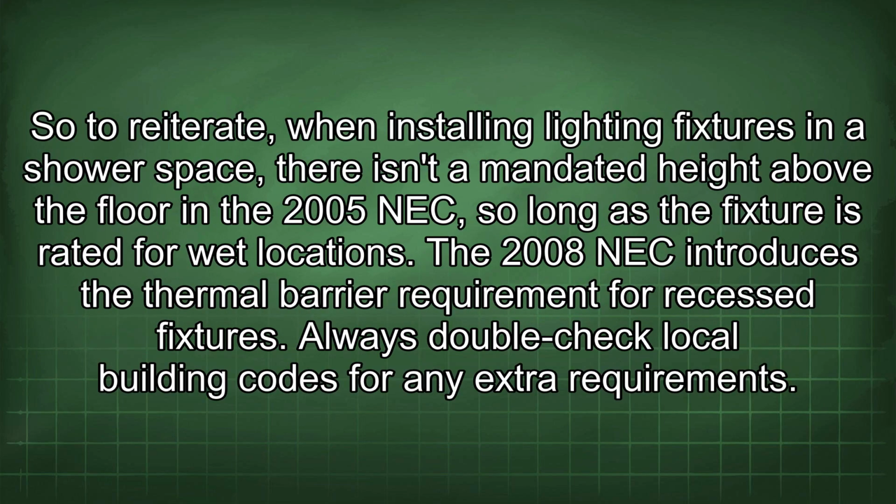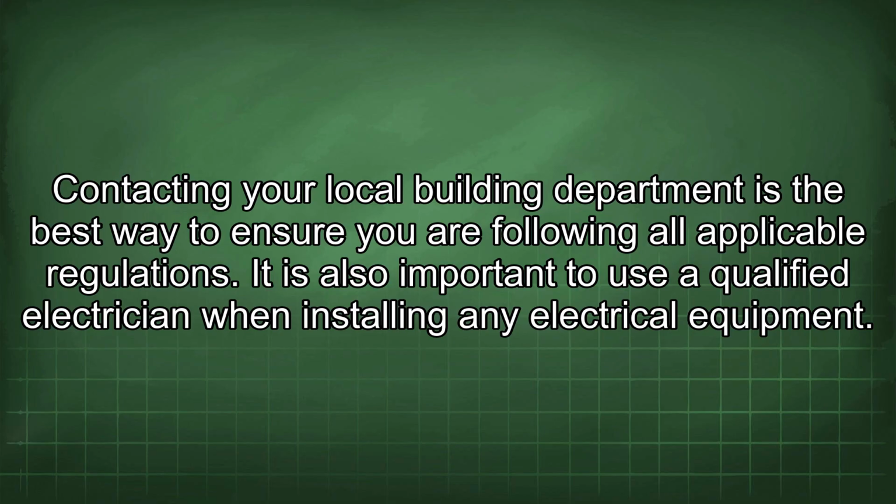So to reiterate, when installing lighting fixtures in a shower space, there isn't a mandated height above the floor in the 2005 NEC, so long as the fixture is rated for wet locations. The 2008 NEC introduces the thermal barrier requirement for recessed fixtures. Always double-check local building codes for any extra requirements. Contacting your local building department is the best way to ensure you are following all applicable regulations.